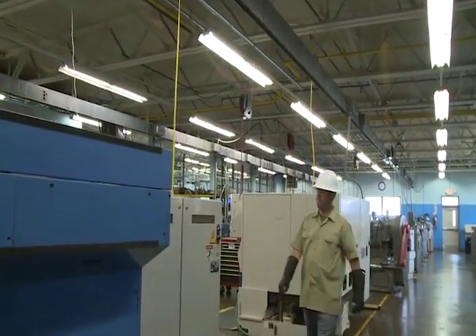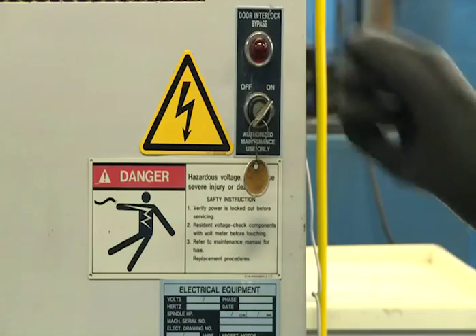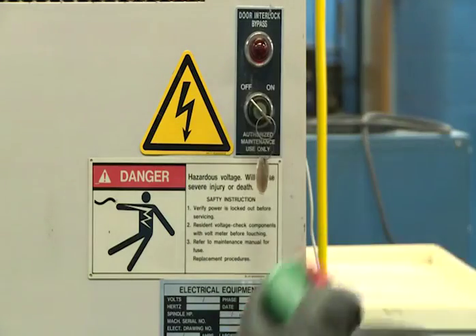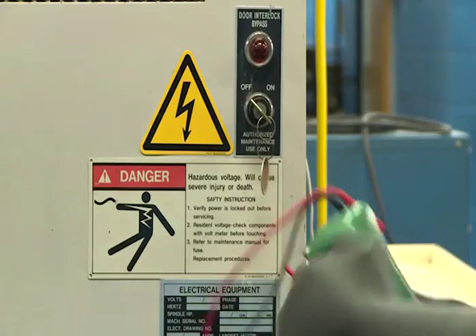The best way to reduce the risk of arc flash is to create an electrically safe working condition before any electrical work begins. This starts with powering down or de-energizing the equipment to be worked on. But there is more to it than that for good reason.